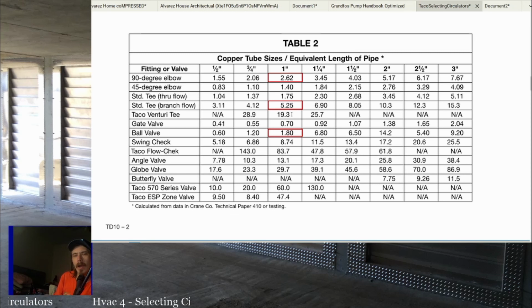You'll know how many radiators or baseboard heaters or air handlers or whatever it may be that are off that boiler system on each zone. So you'll have that information. That tells you probably how many T's you have, right? Because you're going to have to have a T for each one of those in the system. If it's a one pipe system, if it's a monoflow system, then you'll know how many Venturi T's you're going to have in it.